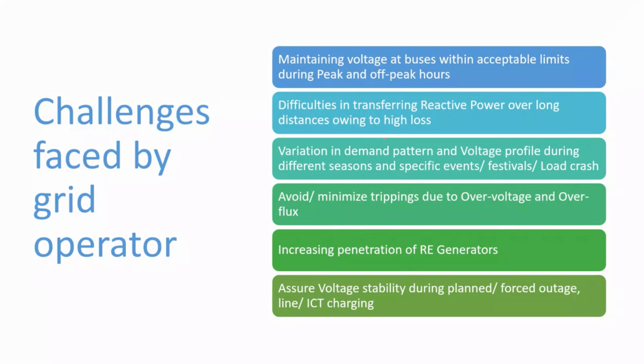So what kind of challenges are observed by the system? I already told you that there are different voltage levels, like 400 and 220. All your equipment is designed at these rated voltages. Whenever you don't maintain the equipment at these rated voltages, it will be under stress, its life will deteriorate, and it also impacts the safety of the equipment as well as the safety of human life at those places. So it is very important to maintain things well within the limits. This is one of the jobs that the operator has to do all the time.